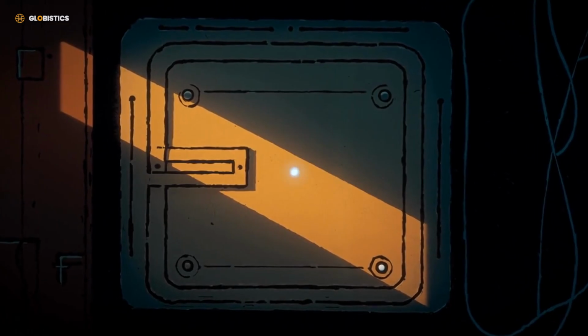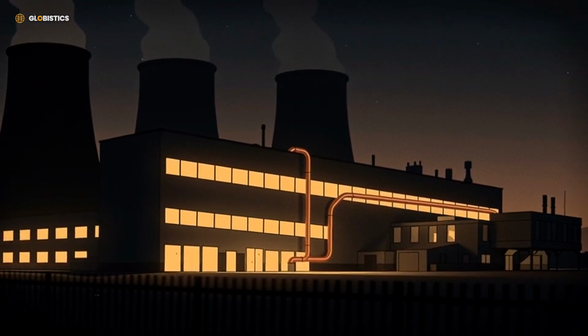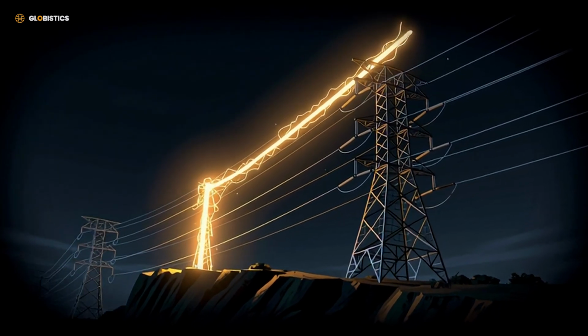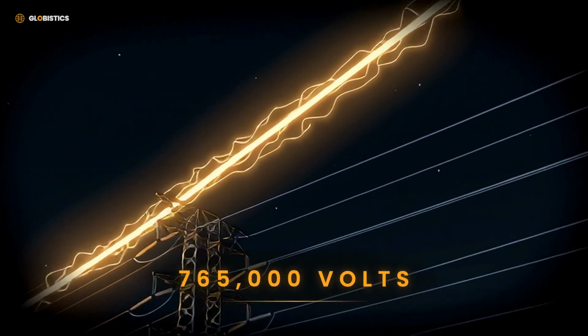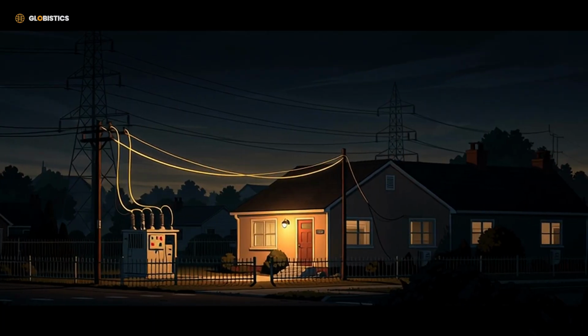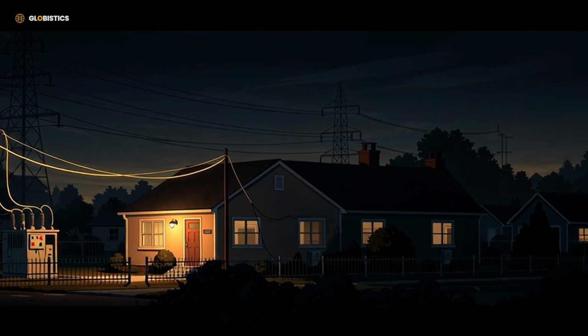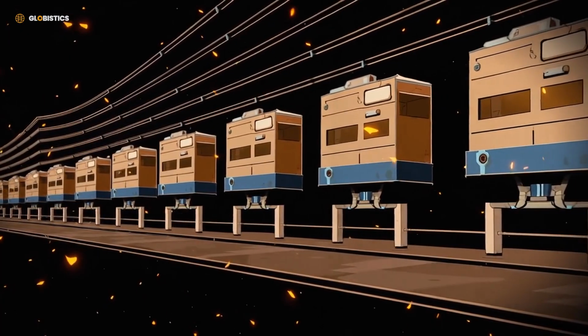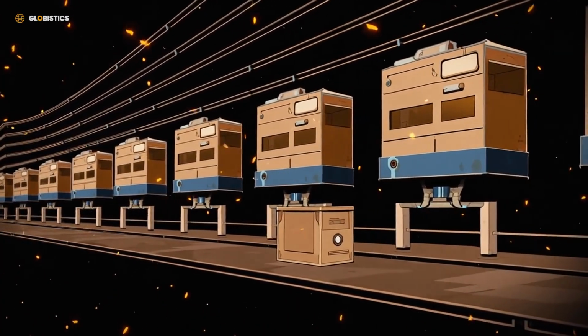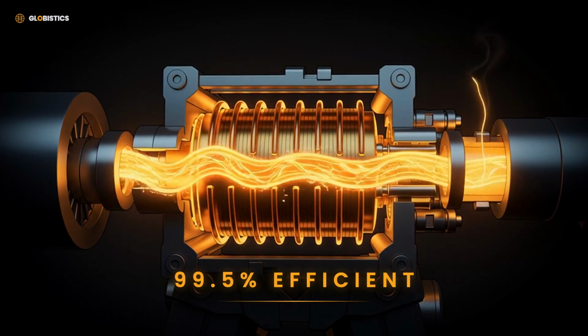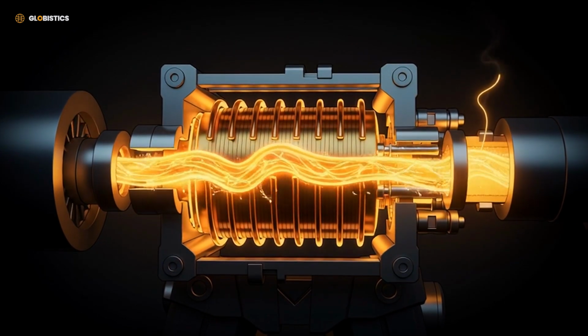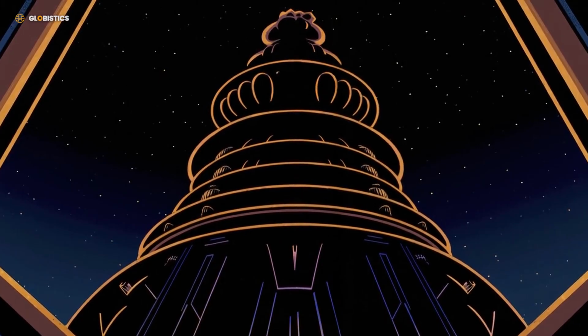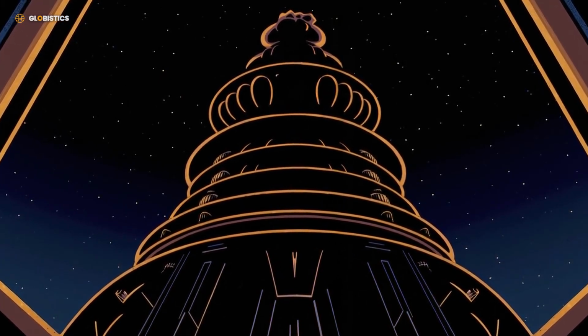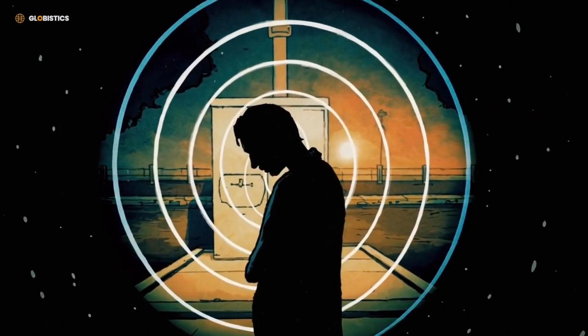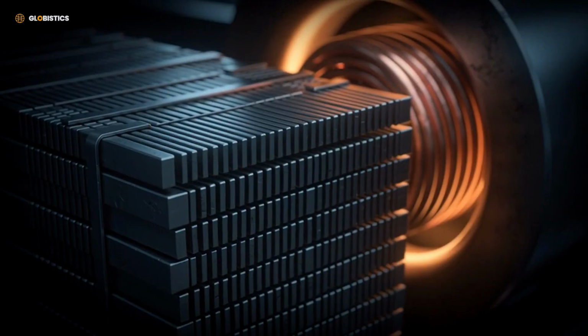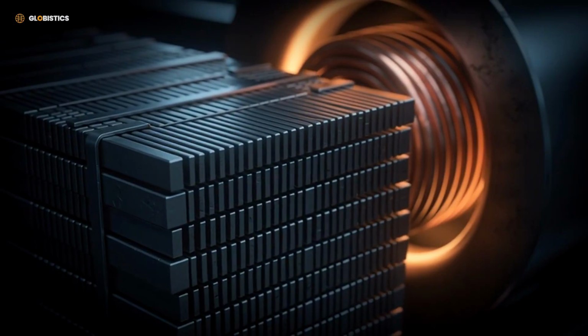Start with what the box does. Electricity leaves a power plant at low voltage. To travel long distances, it is pushed as high as 765,000 volts, then stepped back down before it reaches you. At every point where the voltage changes, a transformer is standing there. It has no moving parts. It converts power at 99.5% efficiency or better, one of the most efficient machines humans have ever built. The hum you hear near one is its steel core stretching by about 1 micron, 120 times every second.